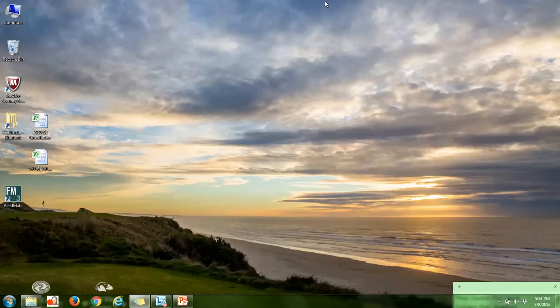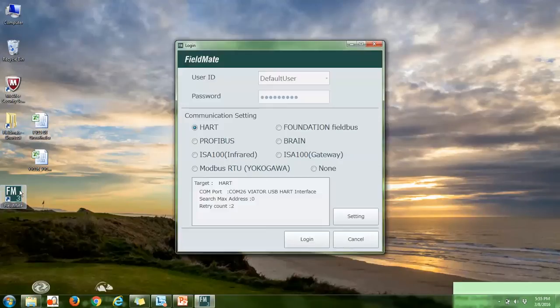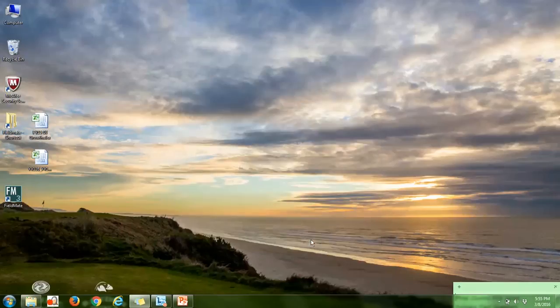So now we're going to connect to Fieldmate to do the trimming that we need to do, because again we're in the scenario that our transmitter's out of tolerance and we need to trim it to get back into tolerance. So we'll pull up Fieldmate on our laptop. This is the opening screen of Fieldmate. You can save a little time by already picking your communication settings. We have a HART transmitter, and based on this little display, I can already see that the modem, the Power Express Plus, has been recognized. That Viator USB is the Power Express Plus, and it's on COM26. So I log in.